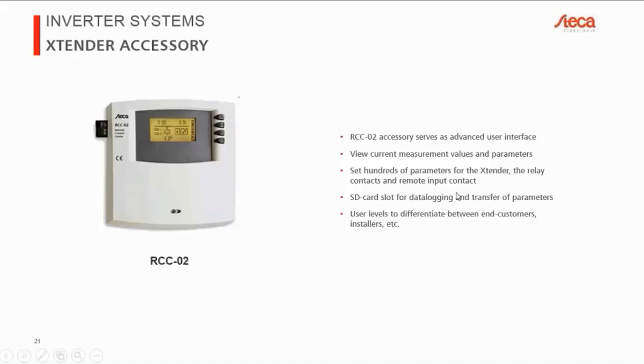Then there's also a remote input contact. So especially for the XTH, and this you can also add to the smaller XTS and XTM. You can also give a signal from the outside to the Xtender. So for example, you can have a switch which you wire to the remote input contact, and then you can program the Xtender to do something when you flip that switch. For example, you can tell the Xtender to switch to the grid if you flip that switch and not worry about synchronization, because the Xtender does that for you. Or you can tell it to stop charging, for example, if you flick a switch, that kind of thing. So you can also give an input into the Xtender while it's running.